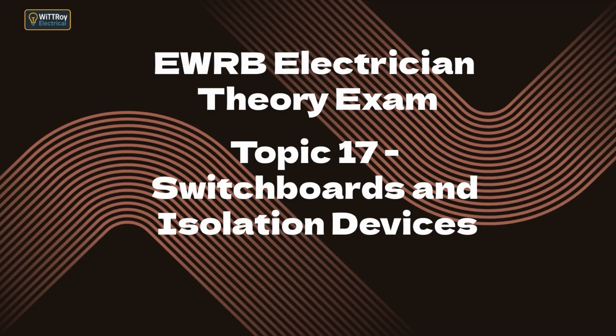Switchboards must have safe access, proper location, fire-resistant construction, correct IP rating, and adequate ventilation. Revenue metering requirements must be met where required by the distributor. Switchboards and switchgear must be rated for the prospective short-circuit current at their installation point. Isolation devices must disconnect all active conductors and be clearly labeled, accessible, and safe to operate.